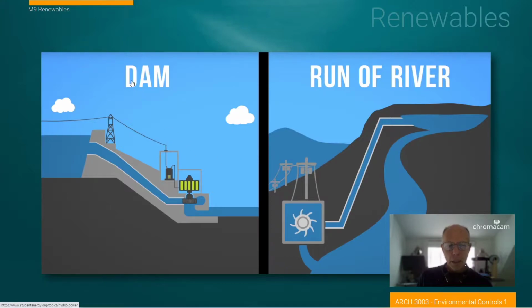One of the reasons why we created a reservoir for the Niagara project was to create a stable amount of electrical flow at all times of the day and all times of the year. And the issue there was the amount of water going over Niagara Falls. We wanted to keep it at maximum output, so we don't remove water for hydropower during the daytime. We only do it at night, and we use it to actually generate electricity directly and also use it to fill the reservoir. So the reservoir in this case is acting as a short-term battery.